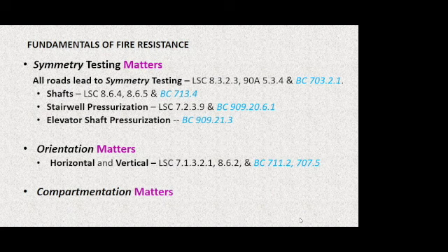And we're going to talk about orientation in the context of the duct moving through the building horizontally or vertically. And that means it's going to be parallel to the other fire resistance rated assemblies in the building that are being built in the horizontal and vertical orientation. So as we move through those fire barriers and those fire rated floor ceiling assemblies and even the roof assembly, we're going to need to be cognizant of the fact that orientation matters, because continuity and support, as the phrase is applied in 707 and 711 of the code, are mandatory for all fire resistance rated systems. And that includes fire rated duct systems. We'll talk about why that matters.